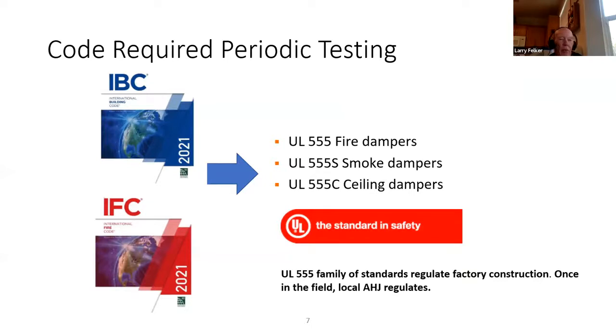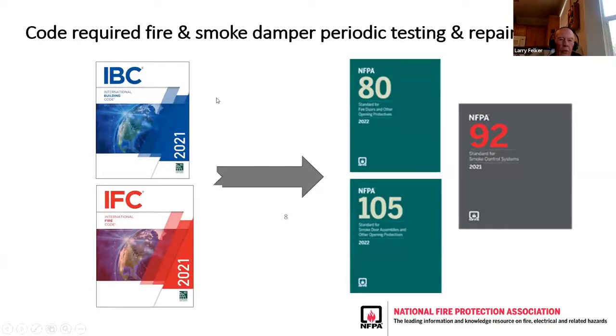NFPA 80 and NFPA 105, which are coming up. I want you to flip slides and we'll get those numbers up there. The codes refer to NFPA 80 and 105 and 92 for testing and for requirements. And those standards require repair of dampers. They do not require replacing.